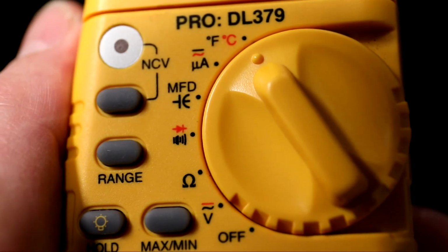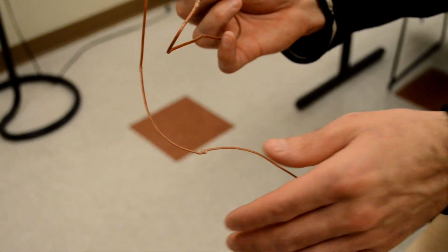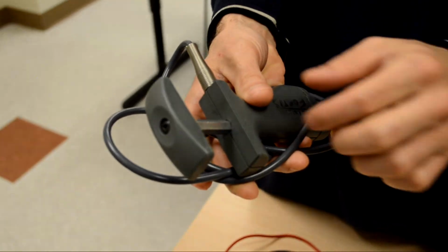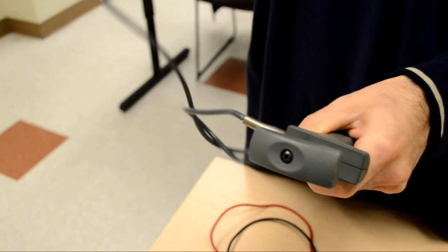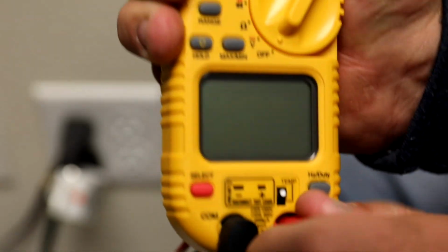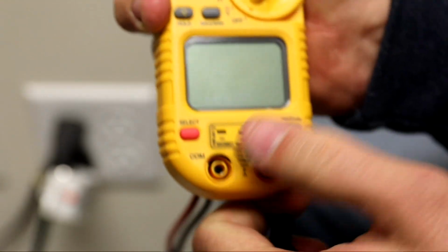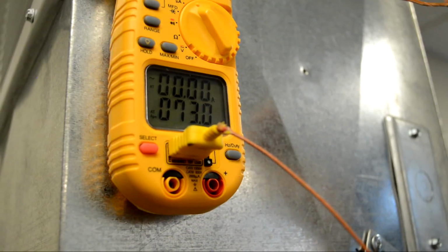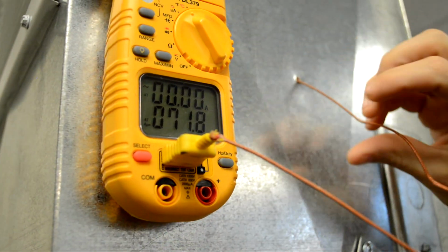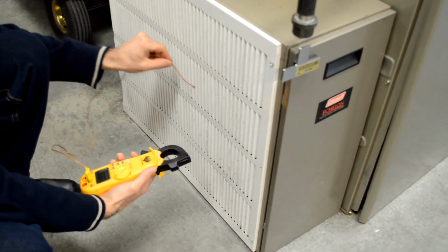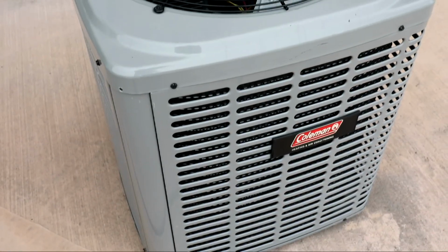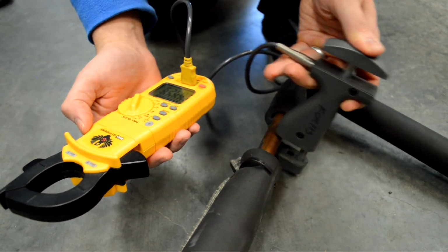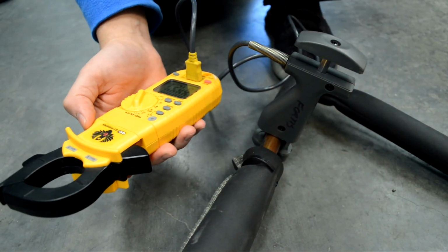Temperature readings are essential in heating and air conditioning. There are two types of temperature sensors available for typical meters, namely the wire probe and the temperature clamp. On this meter, the test leads must be removed in order to turn the temp switch on. With a wire probe, a temperature reading can be taken inside a plenum of a furnace or AC while the equipment is being operated to determine temperature splits. With air conditioning, line temperatures are critical in determining the proper refrigerant level, and the temperature clamp gives us a solid contact with the pipe.